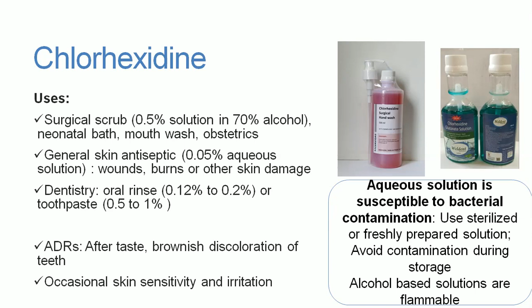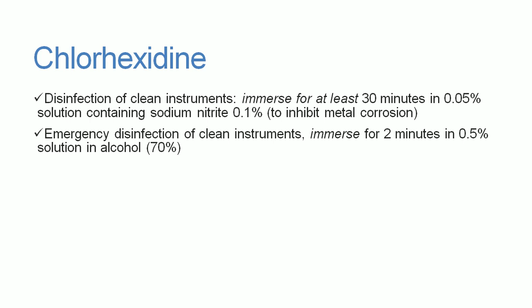Now, chlorhexidine can also be used as a disinfectant. For disinfection of clean instruments, a 0.05% solution of chlorhexidine which contains 0.1% sodium nitrite to avoid metal corrosion is used. The clean instruments need to be immersed in this solution for at least 30 minutes. If an emergency disinfection of clean instruments is required, a 0.5% solution of chlorhexidine in 70% alcohol is used, and these clean instruments need to be immersed for at least 2 minutes in this solution.